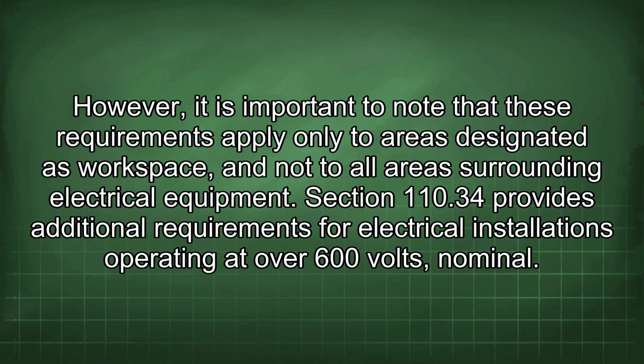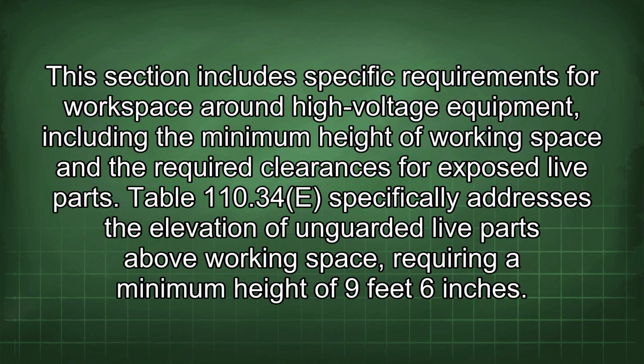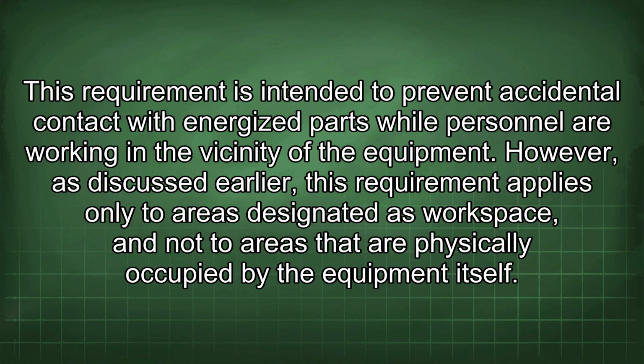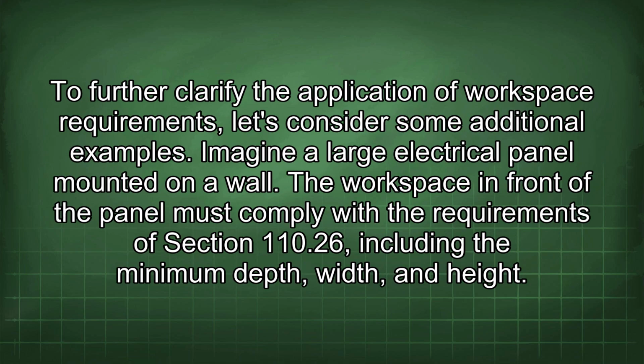Section 110.34 provides additional requirements for electrical installations operating at over 600 volts nominal. This section includes specific requirements for workspace around high-voltage equipment, including the minimum height of working space and the required clearances for exposed live parts. Table 110.34(E) specifically addresses the elevation of unguarded live parts above working space, requiring a minimum height of 9 feet 6 inches. This requirement is intended to prevent accidental contact with energized parts while personnel are working in the vicinity of the equipment. However, as discussed earlier, this requirement applies only to areas designated as workspace, and not to areas that are physically occupied by the equipment itself. To further clarify the application of workspace requirements, let's consider some additional examples.